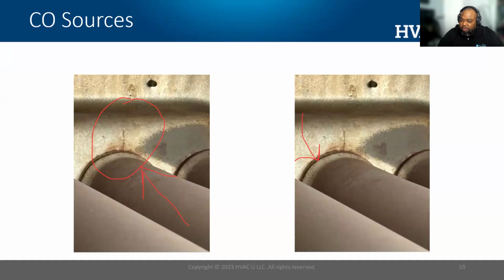And the reason why we have this slide here, the technician that found this issue, they were there at that house for something else. I believe they were there for like a water heater inspection, and when they were doing their CO testing, using their monitor, they found pretty consistent levels of carbon monoxide. And as they dug deeper into it, they found that the furnace actually had an issue. And they saved that family maybe some health issues because they were able to test. And again, they were not there for this specific problem. So testing is absolutely critical to identify these IAQ problems so that you can help keep somebody from being sick or possibly save their life.